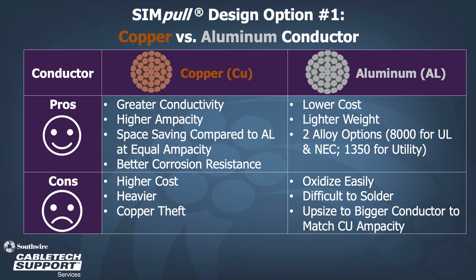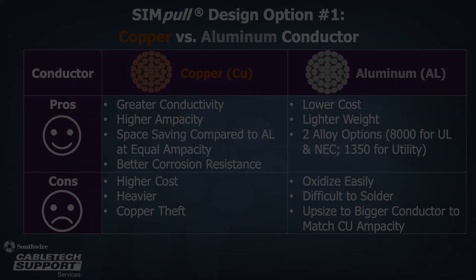For aluminum conductors, the pros are lower cost, lighter weight, and two different alloy options: 8000 series, typically used for NEC applications, and 1350 aluminum, used for utility applications. The cons are that aluminum conductors oxidize easily, are difficult to solder, and you must upsize the conductor to carry the same ampacity as copper conductors.